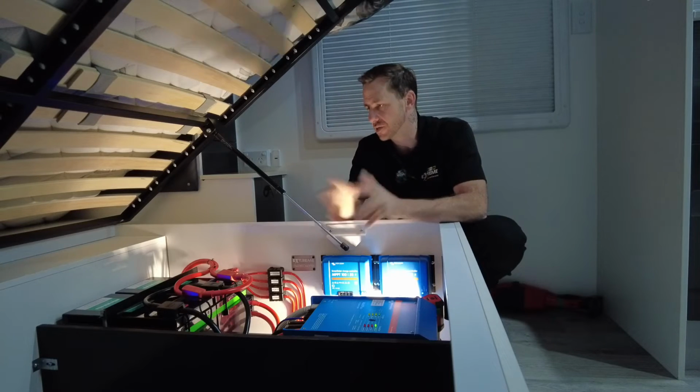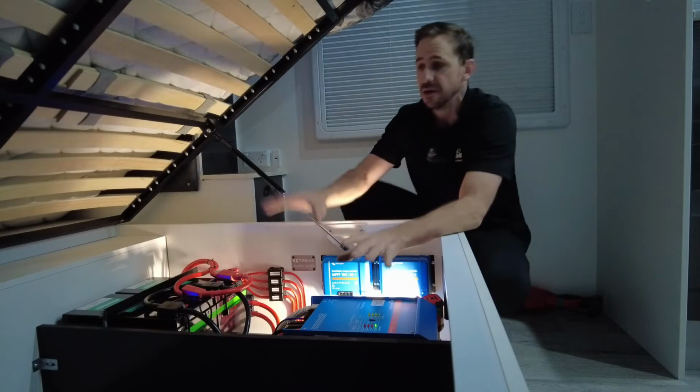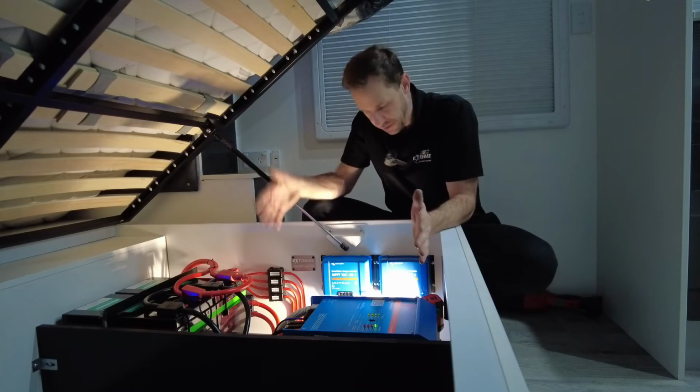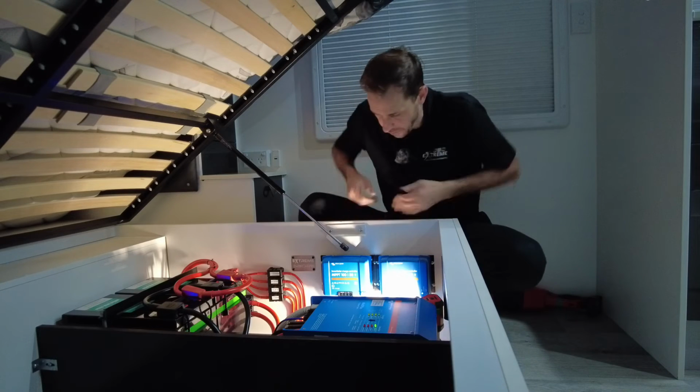So there we have it, guys. Now this is all neatly tucked away. You can see we've got the distribution board on this. We've been able to do that because we've liaised with the customer about what he's fitting in this area, so we can get it there. So that's the setup. It's all easy to read. Anyone can get here, and you've got fuses labeled. It's all neatly spaced out. You can see we've got the vents on the back of these.